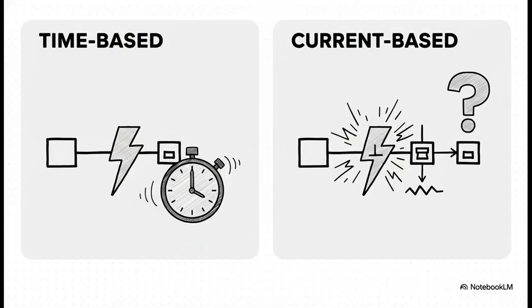So how do we actually do this? Well, the two classic ways are based on either time or current. With time, you just set up a simple delay system. But the problem is, a massive fault right next to a power plant can be allowed to rage for several seconds, which is an eternity in the electrical world, while it just waits its turn. It could cause incredible damage.